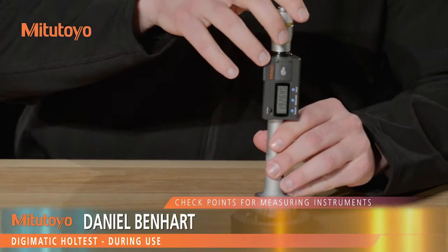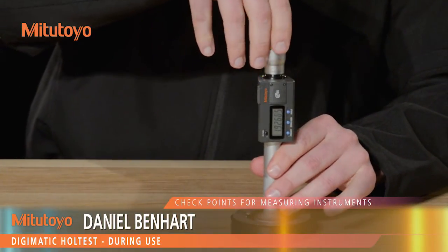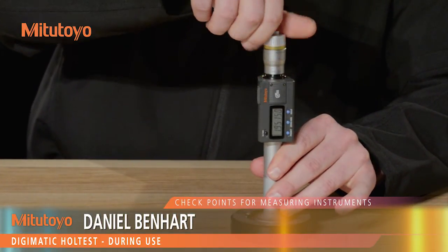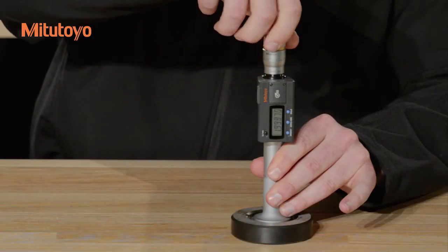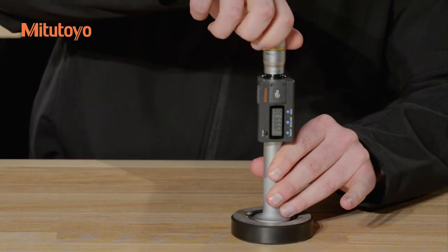To take a measurement, bring the anvils into light contact with the workpiece, then operate the ratchet five to six times to ensure constant measuring force.